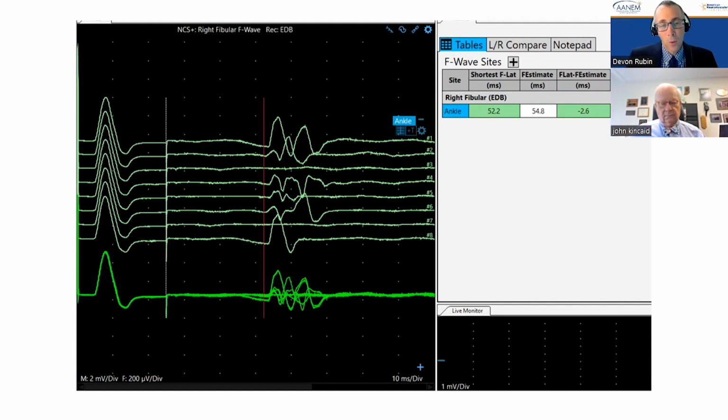Yeah. Okay. We have debates about F waves and the utility of them. I think our rationale is, in patients that we think might have neuropathy, we can't tell if it's a distal neuropathy or a polyradiculopathy. And so in those patients, we'll usually do F waves just to see if there's any clue that it's a more proximal root lesion. I'm absolutely fine with that. And the other merit of the F is it's kind of a quality control on your other values. If the F is normal and your conduction velocity is slow, somebody screwed up, you've got an incorrect distance. So the real merit from my viewpoint is that it's an internal control on your other values in a motor study. Yeah, that's a good point.